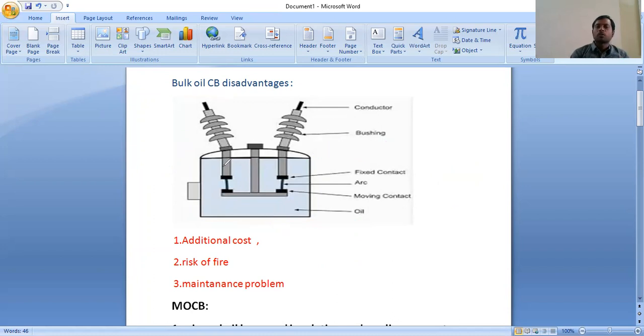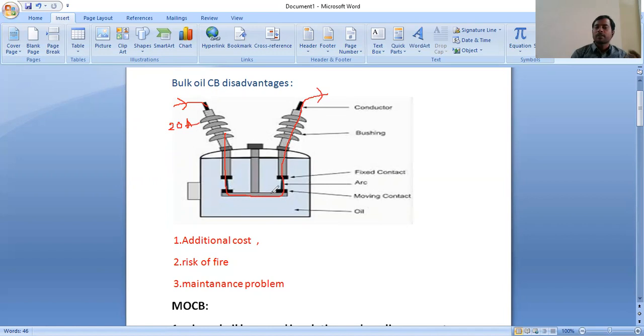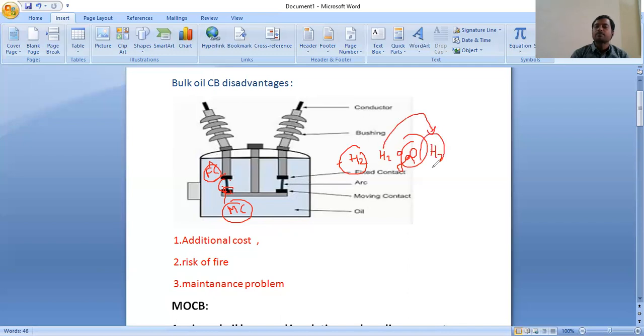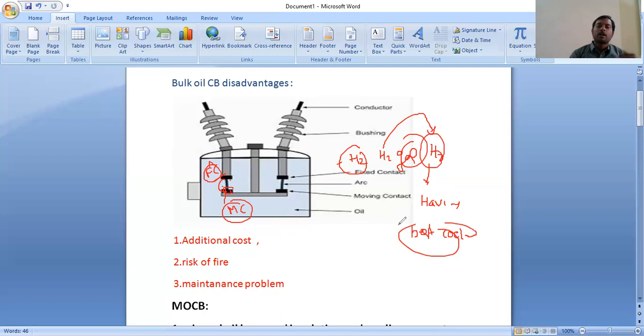The circuit breaker will be like this — this is the incoming line, for example 20 amps, and current passes through the outgoing terminal. Whenever a fault occurs, the relay will give the information to the circuit breaker and the contacts will be pulled downwards. Between the fixed contact and moving contact, arc will be developed. Oil will be filled between the two contacts, and the arc will be neutralized by forming hydrogen gas (H2). H2 gas has the best cooling properties, that's why the arc will be extinguished.